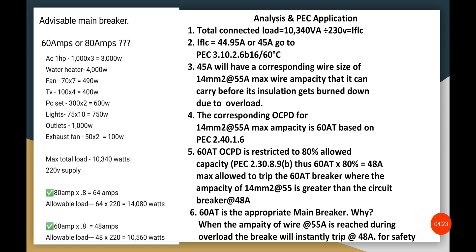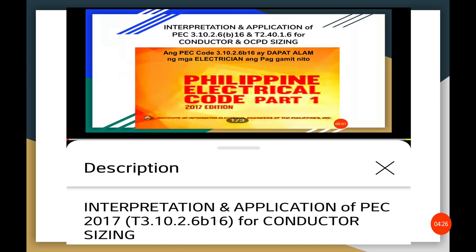This 45 amperes full load current will be based on PEC 310.2.6b16, at the 60-degree column. Why 60 degrees and not 75 degrees? Because there are rules and regulations in the PEC 310.2.6b16 that govern which column to use. I recommend watching my previous vlog on how to interpret PEC 310.2.6b16 to understand the rules for the 60, 70, 75, and 90-degree columns.